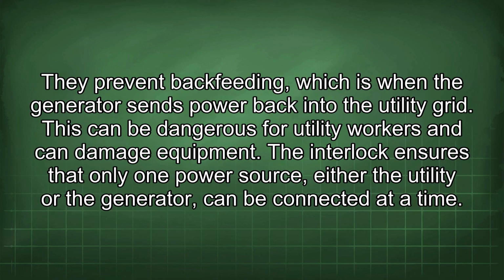Interlock mechanisms are essential safety features. They prevent backfeeding, which is when the generator sends power back into the utility grid. This can be dangerous for utility workers and can damage equipment. The interlock ensures that only one power source, either the utility or the generator, can be connected at a time.